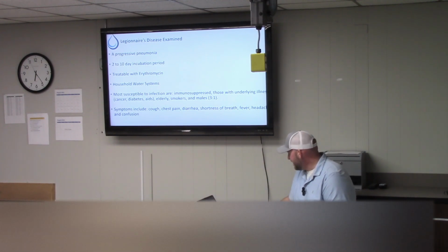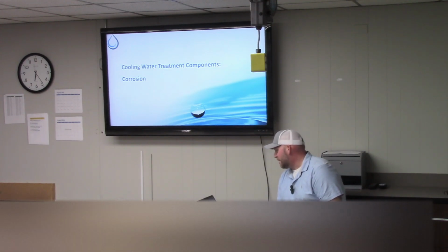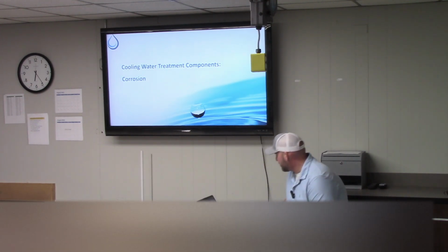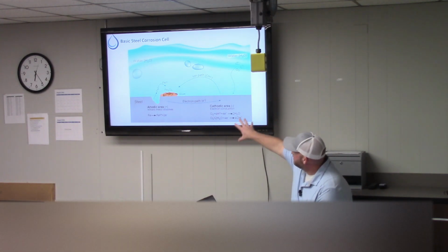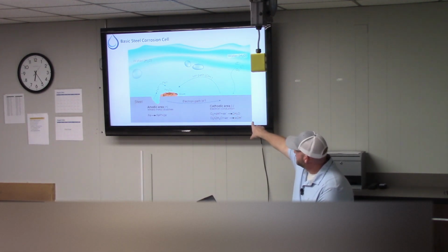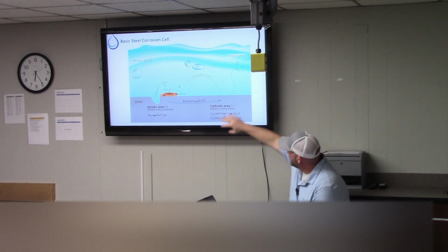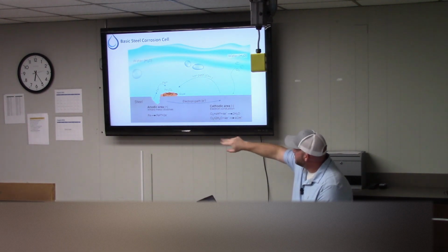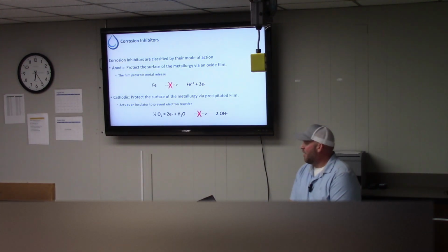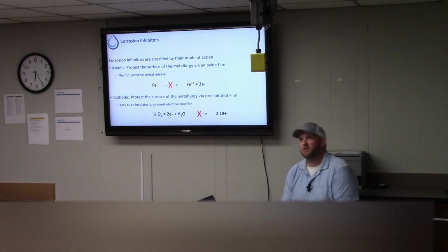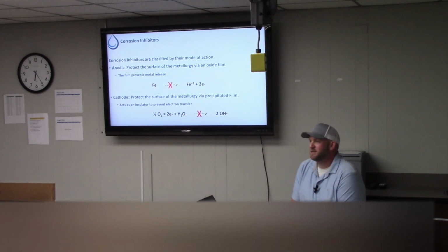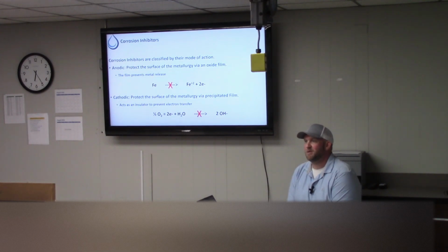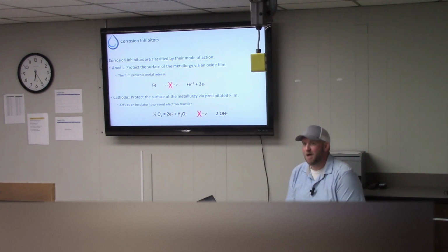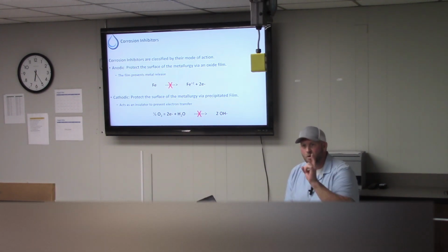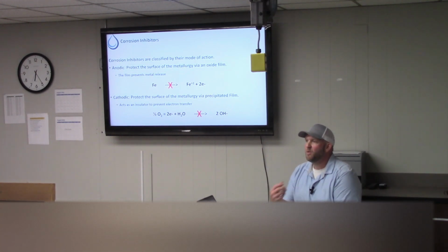Okay, let's stop here and talk about the ways we inhibit corrosion. We talked about our basic corrosion cell — anodic and cathodic areas, the free flow of electrons, and that path always going from the anode to the cathode. It's our responsibility to find a chemistry we can put in the water that inhibits that corrosion from occurring. We can't get rid of the water, we need that, and we can't get rid of the free flow of electrons — that wants to happen if those two sites exist. But what we can do is block the cathode, or block the anode.